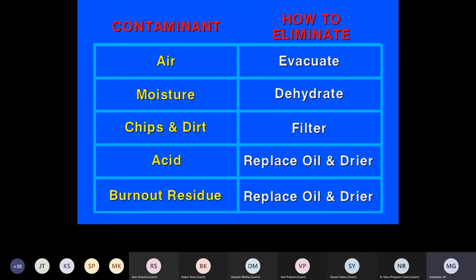So naturally, if moisture and refrigerant combine, they can form hydrochloric acid and hydrofluoric acid. Both are certainly dangerous, because they can form acid, which can further damage the winding or the completely internal copper. So it's a chain reaction. So whenever a compressor fails and we quickly replace it, then within no time we can see a repeat failure.